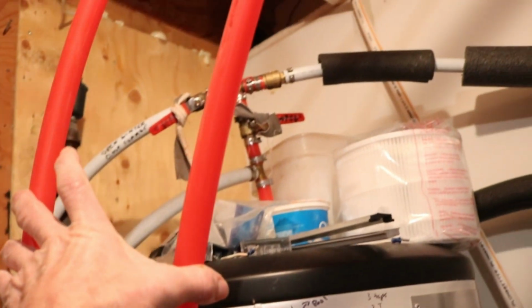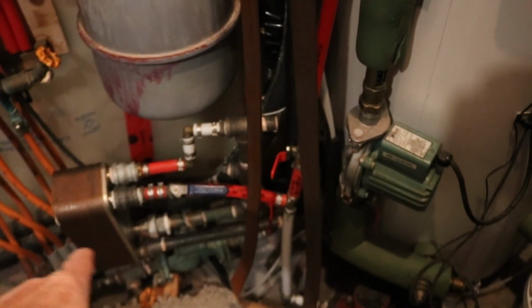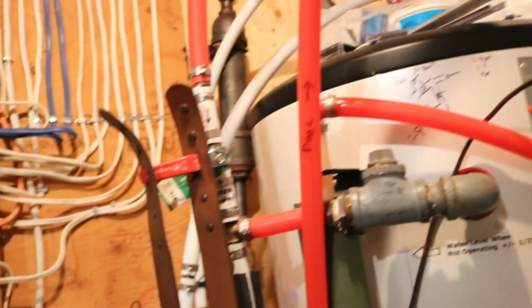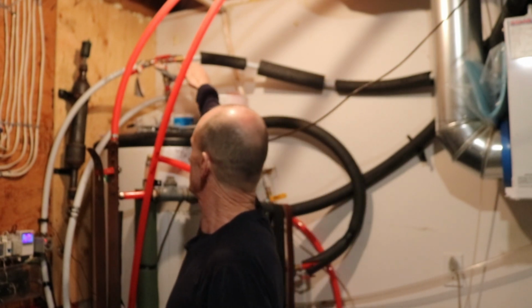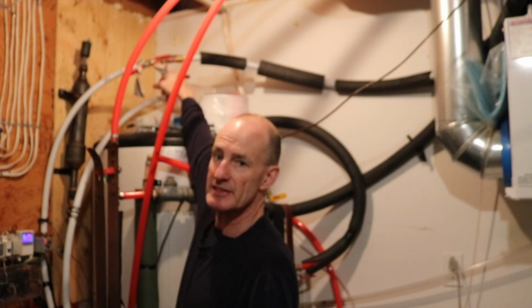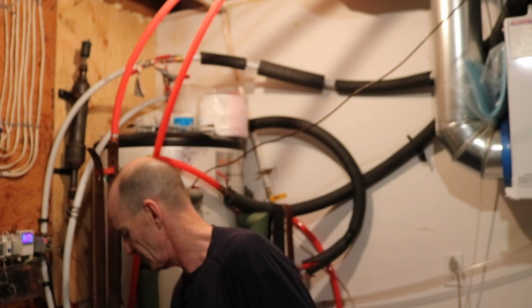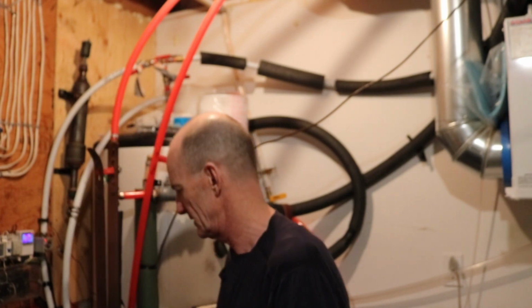There's my expansion tank up there. And then these two pipes that are now feeding the floor heat, they shut them off and they go to the pool. Alright, I know that sounded pretty complicated for you, and it is for me. But here, for the summer, we turn this here so the water just goes right into the tank. It doesn't go through the rad. And down here, turn these switches opposite so it doesn't go to the floor heat. It goes to the pool. And then we just shut off that breaker. When we shut off the heat breaker to the relay, the pump still is able to pump because it's normally closed. And when it gets power, it goes open and stops the pump. So it's normally closed.